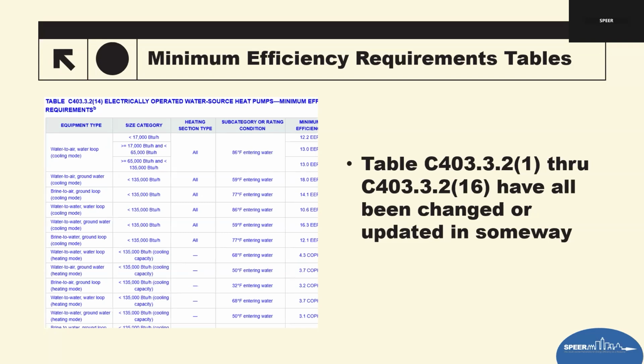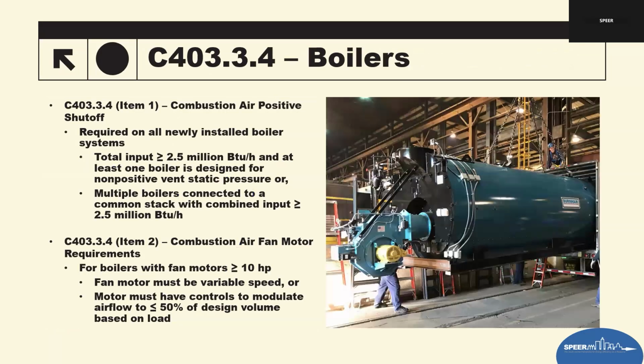These tables form the baseline. So this is your starting point for HVAC efficiency in commercial buildings. If you're reviewing mechanical plans, you cannot assume a unit that passed under the prior code will now pass in the 2024. So you've got to verify that all over again. Designers must verify every listed HVAC unit against these updated tables.